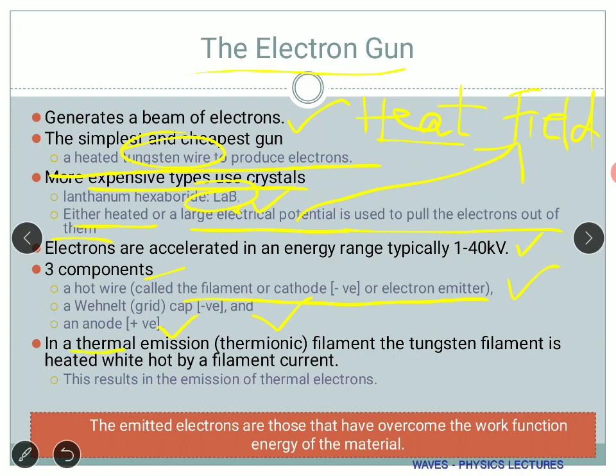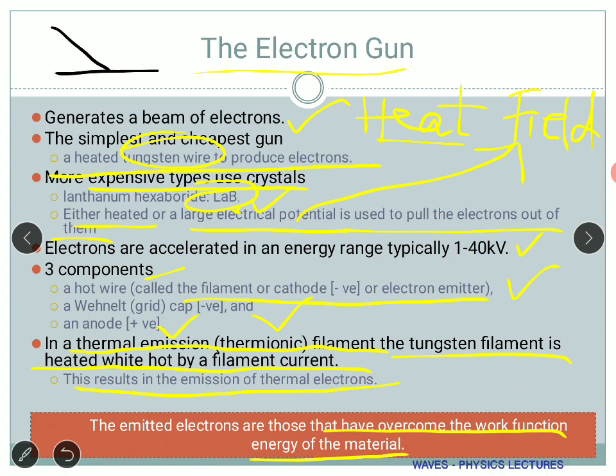For thermal emission — where you are heating — the tungsten filament is heated by filament current, applying a huge amount of current which causes the filament to heat up. When the filament gets heated it emits electrons called thermal electrons due to the temperature. These emitted electrons are those which have overcome the work function energy of the material — similar to the photoelectric effect where a metal surface ejects an electron when radiation of sufficient energy falls on it.